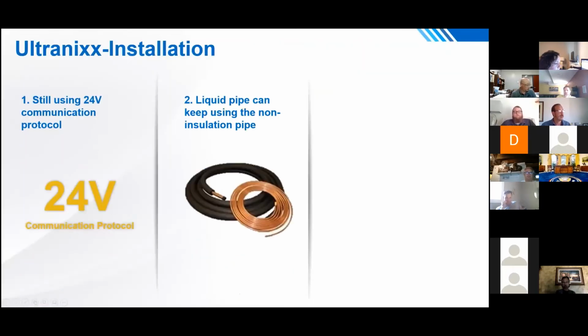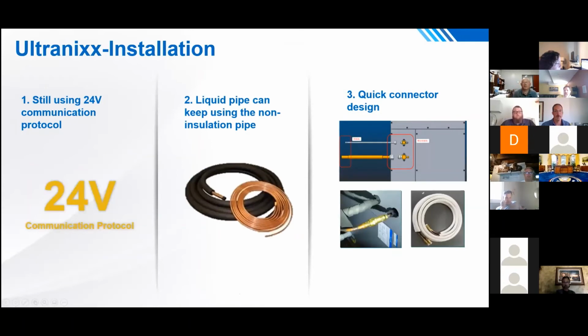Okay. Jeff, you want to handle this part? Sure. Okay. Talk a little bit about the Ultranix installation. We are talking about inverter-driven compressors. If a lot of you guys are familiar with that, you'll know that normally they require DC communicating voltage and a special thermostat. This unit is still using 24-volt protocol. So with that, we can use a standard heat pump thermostat, nothing special, just anything off the shelf.